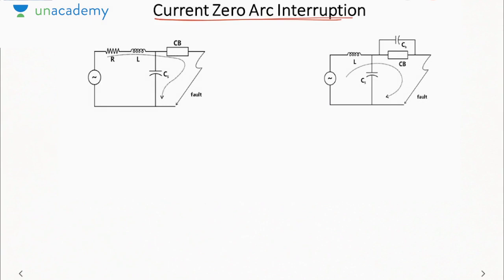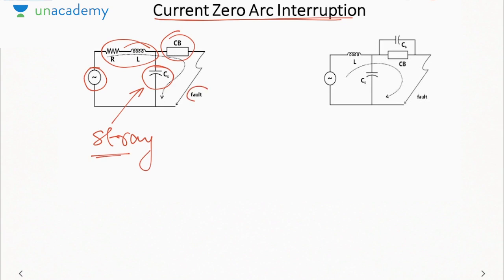That means we need to interrupt the arc whenever the current is zero. So let us consider a case when we are interrupting the arc when current is non-zero. See, this is just a generator, a transmission line, and the transmission line capacitance or stray capacitance. Then there is a circuit breaker and a fault occurs here.